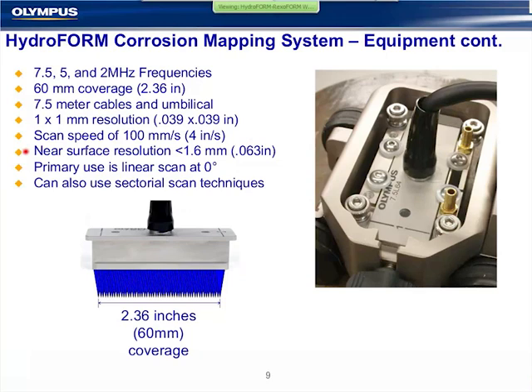We define the near surface resolution as the ability to detect the flaw within that distance of the outside surface. And for the water column, we get an optimized pipe to water interface, which minimizes that, and it's about 1.5 to 2 millimeters depending on the surface condition. For those of you who are OmniScan users and know the wizards, this uses primarily the linear scan at 0 configuration as opposed to sector or linear scan. And of course, multiple groups can be used at the same time using the linear. So we can do angle beam and 0 degree through the same probe at the same time in 2 separate groups.